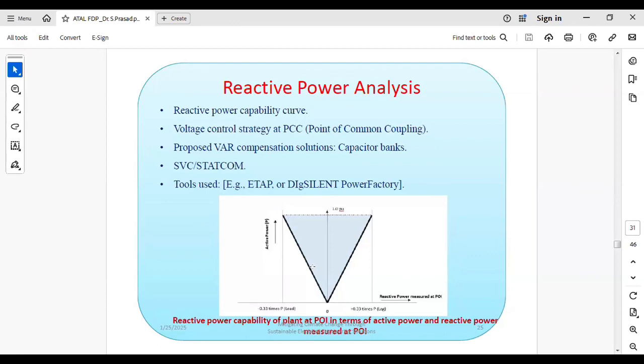As you know, capacitor banks, STATCOM and SVC are the reactive power compensating devices presently available, and STATCOM has the most dynamic performance, better than capacitor banks and SVC. So what should be the size? It is a very serious issue that you have to do this test so accurately and find the accurate size of the STATCOM, because the cost of a STATCOM per MVA is very high. If you increase the size of the capacitor bank or STATCOM, the cost of investment will be more. So you have to optimize the size of the STATCOM or SVC or capacitor banks. You need to specify the accurate value by conducting this reactive power analysis test.